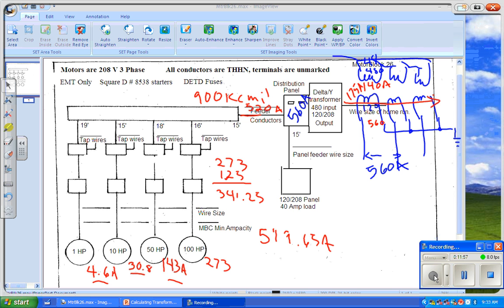What we need to pick up out of this for the moment is that we would have to have 175 amp wire, however many feet going back for this load. Now that's a good thing in a way, because instead of having 900 kcmil on the conduit going all the way back, this is much smaller. And that might play into which way is cheapest to do this. Because one of the things you're going to have to do is watch the customer's money like it was your own, right? So you have to calculate, well, which way is the cheapest way to do this job and still create an efficient system? So one of the things you need to do sometimes is ask, can I avoid using this transformer, or can I avoid using such a big transformer? And what is that going to be cost difference in wire size and conduit? And that comes down to estimating. And when you go out on a job as an owner or a foreman, a lot of times you have to estimate, and that's where this is coming from.